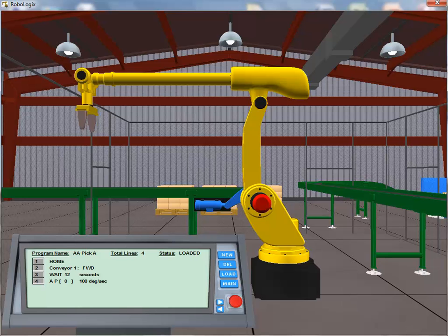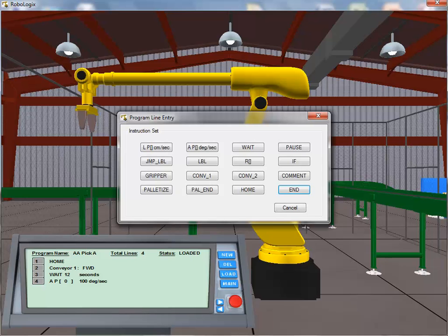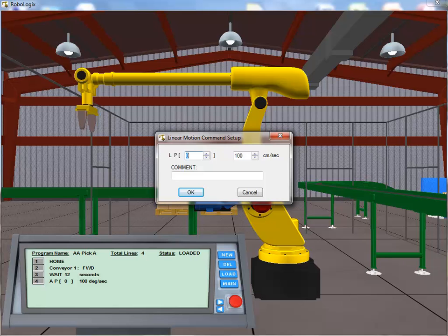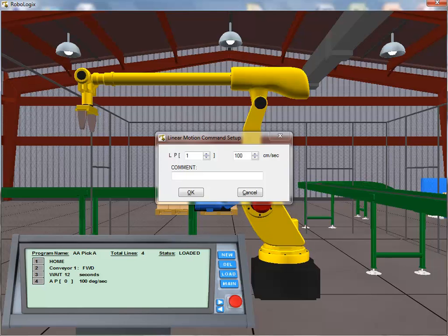Once again, we click on the New button to add our next instruction. This time, we're going to move the robot arm straight down to the conveyor, so we select the Linear Motion instruction. The Linear Motion command setup dialog box allows the user to specify the position register index location. In addition, the user can define the velocity at which the motion occurs. As this is a separate location from the first one we moved to, we set the index value to 1. We then click on the OK button to add the instruction to our program.